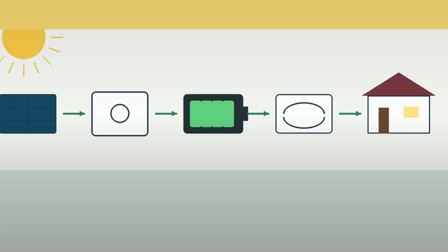Run a charge cycle. In good sun, watch current flow into the battery and confirm the controller reaches the expected stages for your battery type. Then run a discharge test with normal loads. Watch voltage sag. Watch inverter temperature. Watch cables near terminals. If anything gets hot, smells wrong, flickers, or trips, stop and diagnose before leaving the system unattended. Label the system after it works, not before.